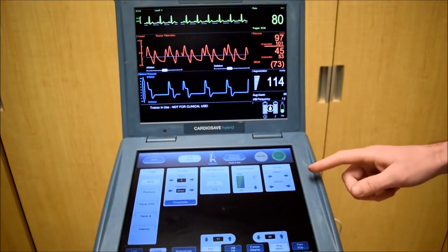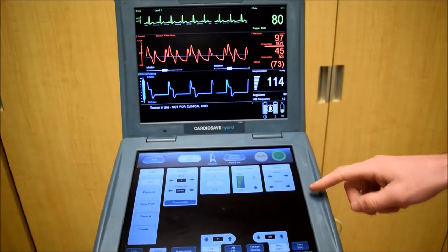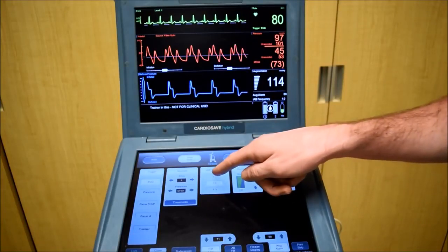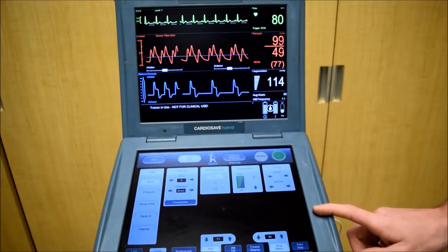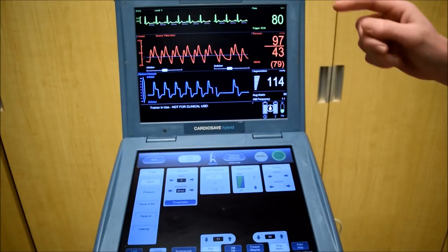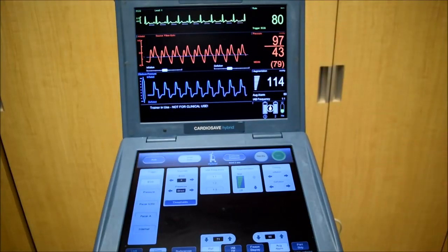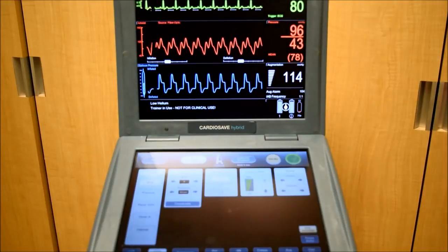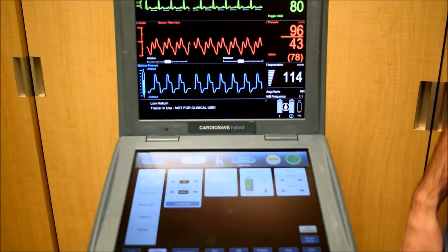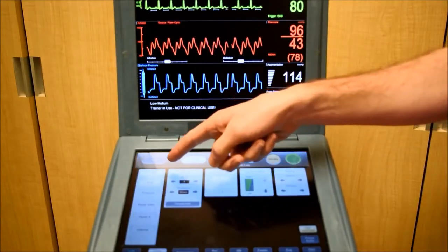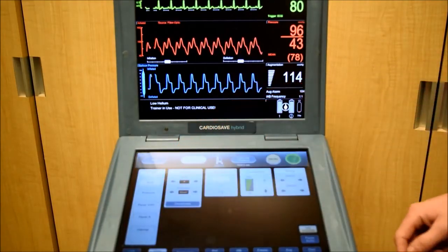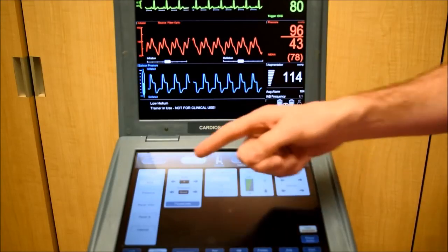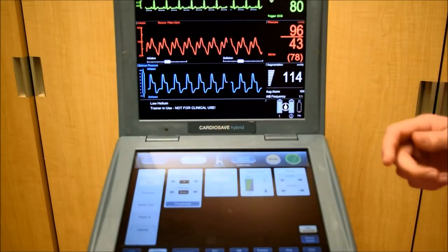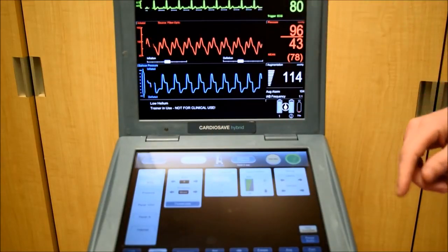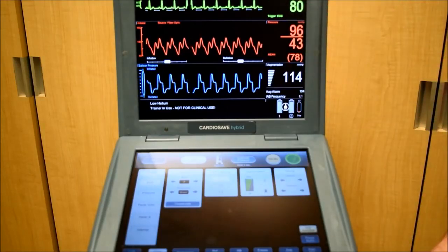Now that we've timed both inflation and deflation, I'm going to put the balloon back in 1-to-1. This will mean that each beat will be assisted. I'd like to talk about the trigger source for a minute. Your trigger source can be found on the left side of the lower monitor. Right now it's an ECG. This means the balloon is timed based on the ECG.